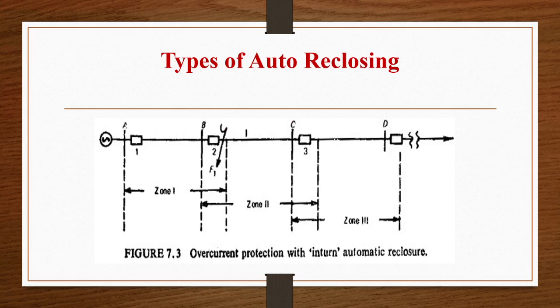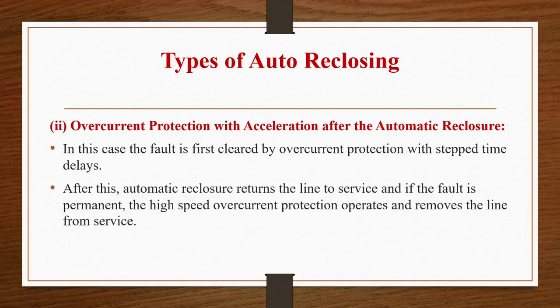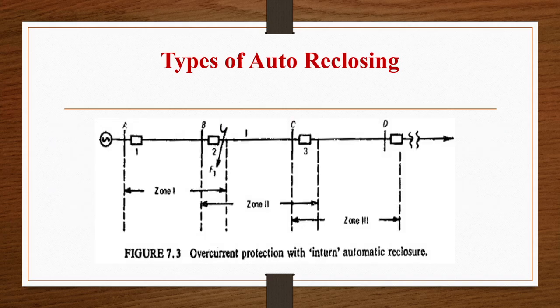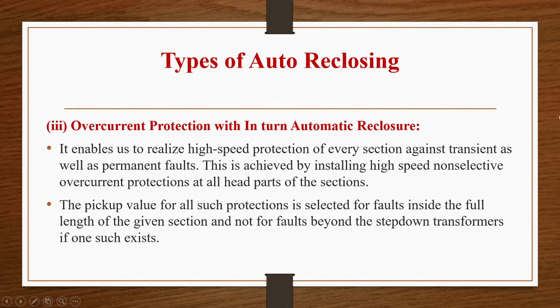So this is the diagram showing overcurrent protection with acceleration after automatic reclosure, where we can see there are three zones. Stepped means what? Here I have mentioned the delay as a stepped time delay. Okay, so this is the stepped time delay. Three zones are shown here: zone 1, zone 2, zone 3. This is the occurrence of the fault and the line. F1 is the fault here, and this is the generator, and this is the line. This is a single line diagram for overcurrent protection. Now let us see the third one, that is overcurrent protection with in-turn automatic reclosure.